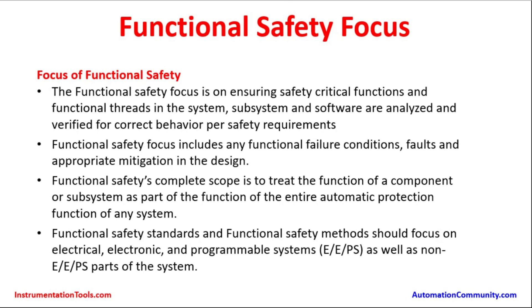Functional safety's complete scope is to treat the function of a component or subsystem as part of the function of the entire automatic protection function of any system. There are many subsystems within a major system, so everything has to be automated. Functional safety standards and methods should focus on electrical, electronic, and programmable electronic systems as well as non-electrical/electronic programmable systems — such as safety relief valves, PRVs, PSVs, and rupture discs to relieve pressure, and dikes. These are all non-EPS because they are mechanical protection devices, not electronic.